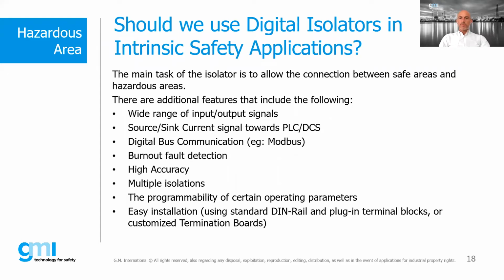There are units with digital bus communication, for instance Modbus. There are units with burnout fault detection, especially for temperature, high accuracy multiple isolators, units with programmability of certain operating parameters, and also units that can be used in different installations, for instance on DIN rail, also DIN rail with a power bus, or with customized termination.